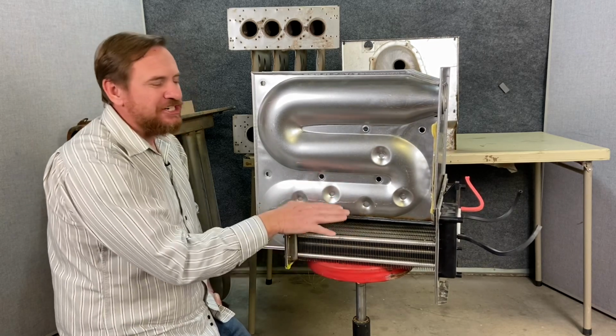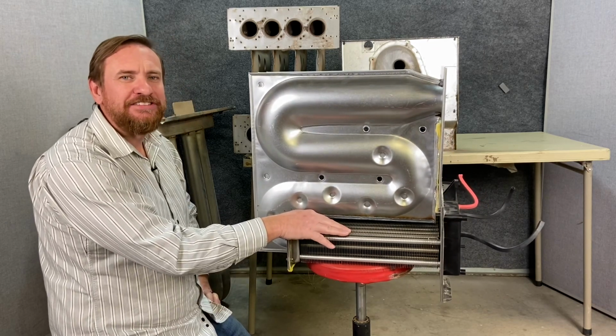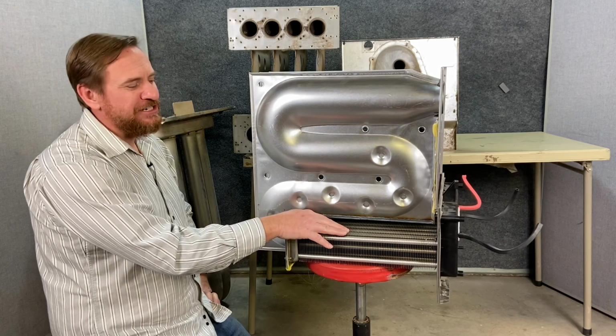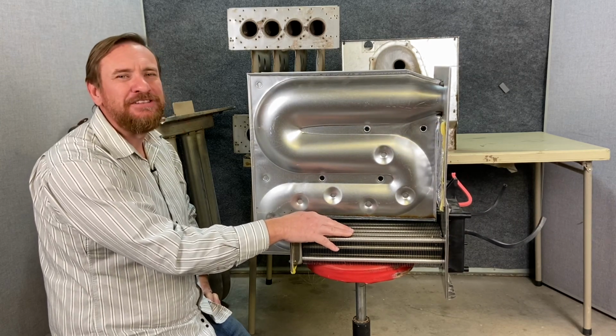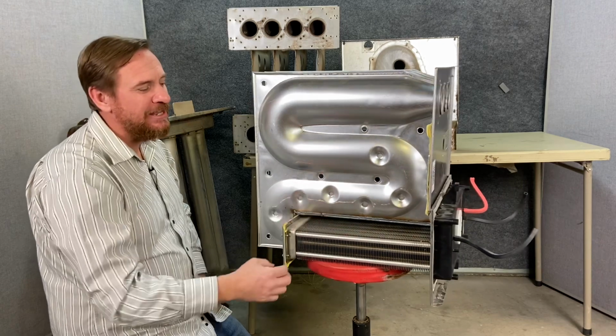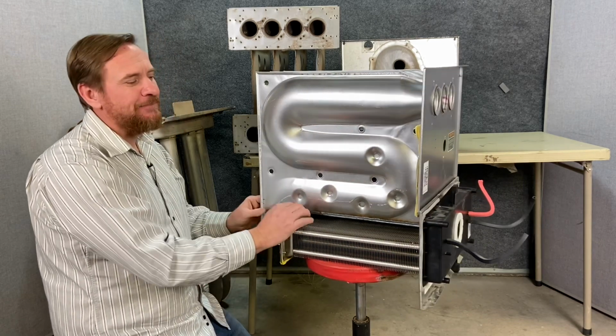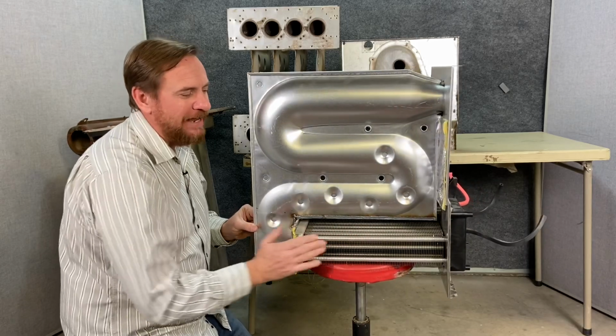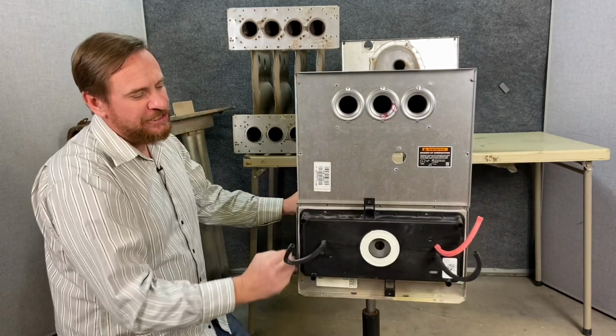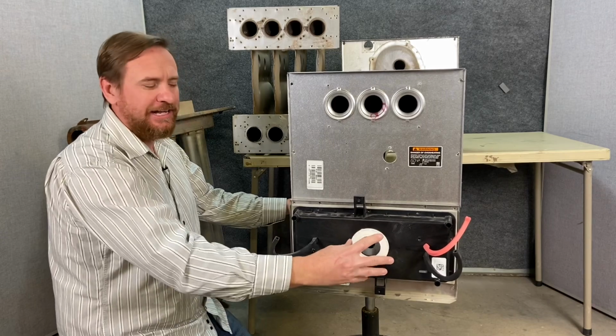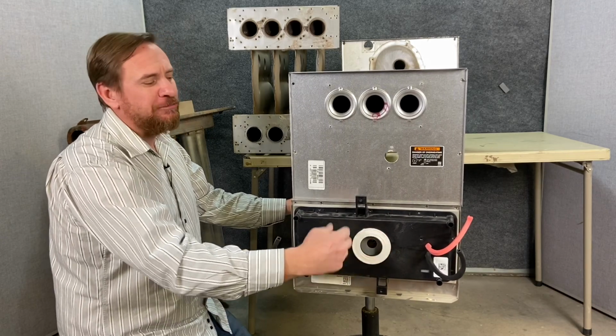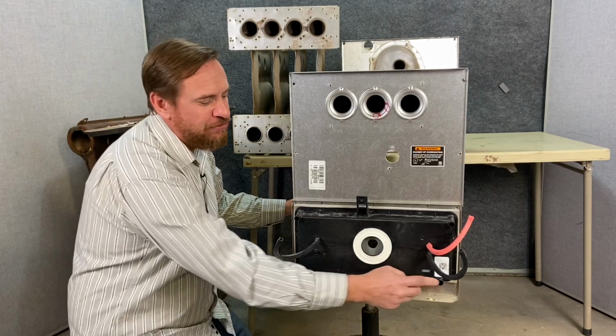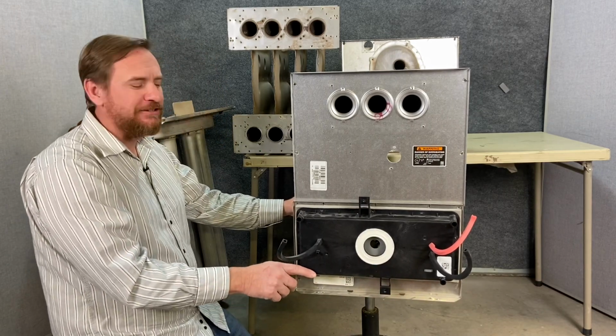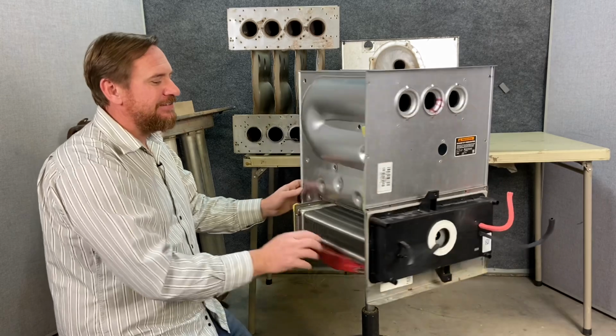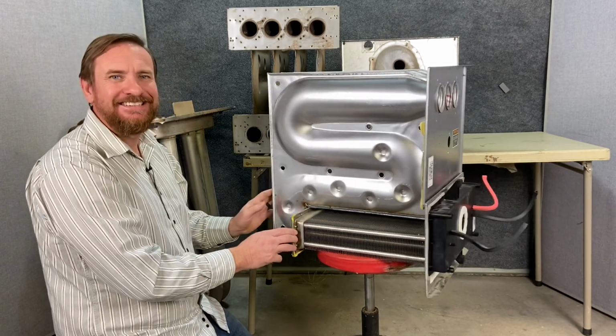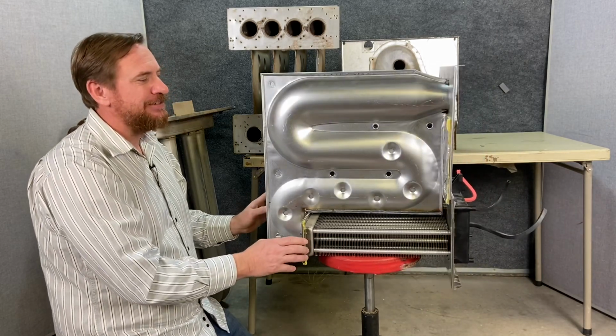In the secondary heat exchanger, we have condensing going on. It's changing state from a vapor to a liquid. As we're changing state from a vapor to a liquid, that's 970 BTUs of extra heat that's rejected. So that's even more heat we're getting into the house. Because it's condensing in here, that's why this is made of stainless steel. And our collection box here is also made of plastic, and our inducer fan motor is plastic as well to be able to account for the water. And we also have drains on this. So we're going to have to drain the system even in the summertime. But this is our 90 plus high efficiency condensing gas furnace, all the way up to 98% efficiency nowadays.